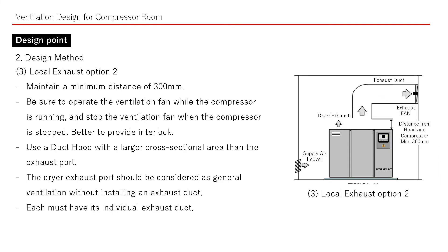About local exhaust Option 2, using a fan for inside the duct. 1. Maintain a minimum distance of 300 mm. 2. Be sure to operate the ventilation fan while the compressor is running, and stop the ventilation fan when the compressor is stopped — it is better to provide an interlock. 3. Use a duct hood with a larger cross-sectional area than the exhaust port. 4. The dryer exhaust port should be handled as general ventilation without installing an exhaust duct.